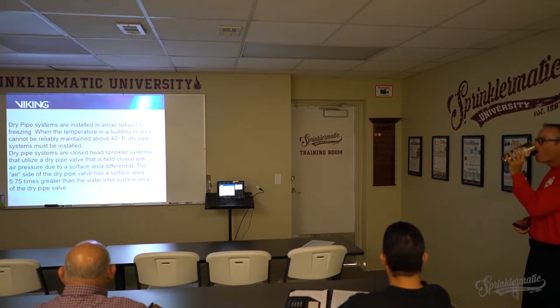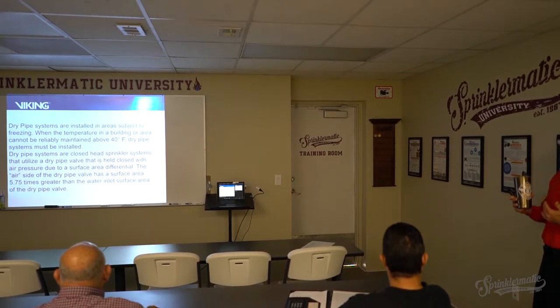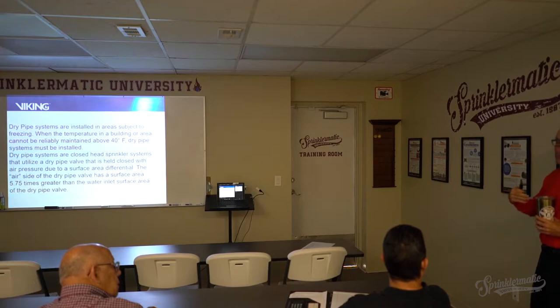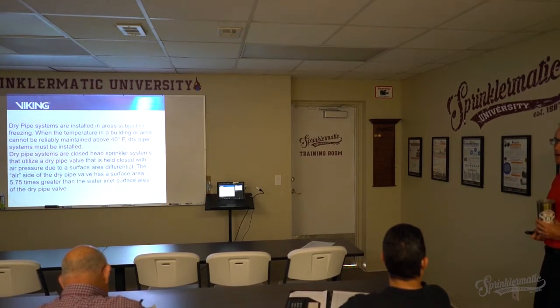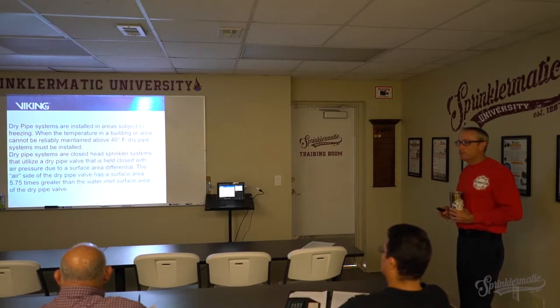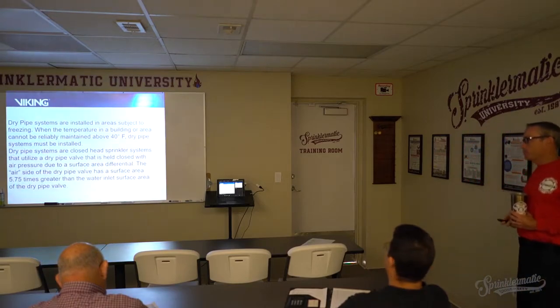And in Florida, there actually is what NFPA, I guess, would determine to be a freeze line. I want to say somewhere around the Orlando area is where you're going to start seeing more dry pipe systems, because the temperature drops below 40 quite often up there. But down here, you're definitely going to see them in freezer storage, cold storage docks, and the preaction systems where you were just describing as well.